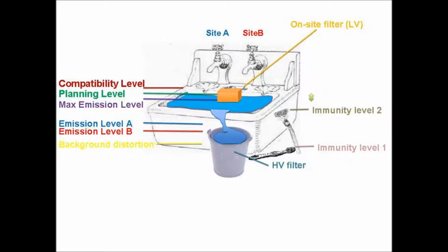And supposing you've got a leak onto the system. In this case, it's your background distortion. There's always stuff on the system that's harmonic related, from transformers or from small-scale users, and in your own home, your laptop charger or whatever it happens to be. It generates stuff and puts it up there. And in small amounts, it can get to whatever level. So that's the background distortion. It's going to take up so much of it. And then you've got whatever is between that yellow line and that purple line to fill with any site that comes in. And you don't really want to fill it if you can help it.